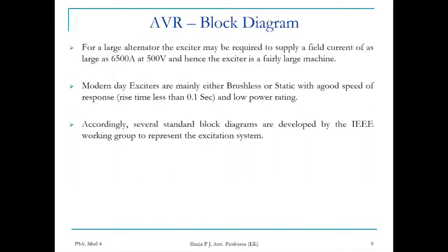For large alternators, the exciter may be required to supply some megawatts of power, and hence the exciter is a fairly large machine. Modern day exciters are mainly either brushless or static, with a good speed of response and low power rating compared with the older versions. Accordingly, several standard block diagrams are developed by the IEEE working group to represent the excitation system.